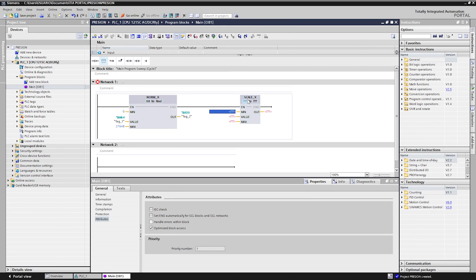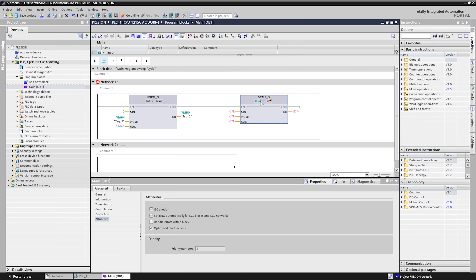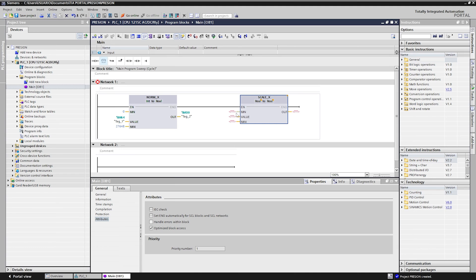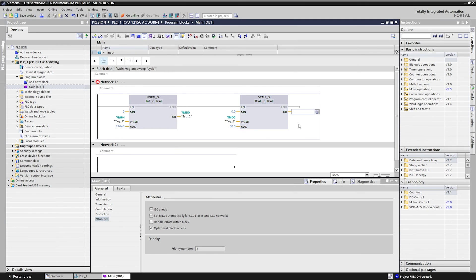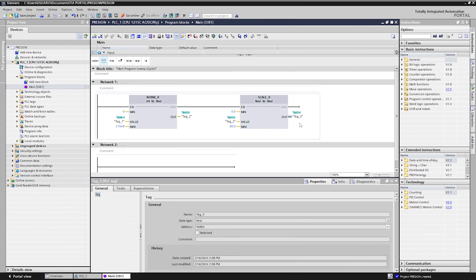In the scale block, we convert real data to real. The pressure transmitter has a capacity of 0 to 60 psi. We place that information in the PLC. We set it to a minimum of 0. In value the memory MD0. At max 60 psi. Finally, add out an MD4 memory.